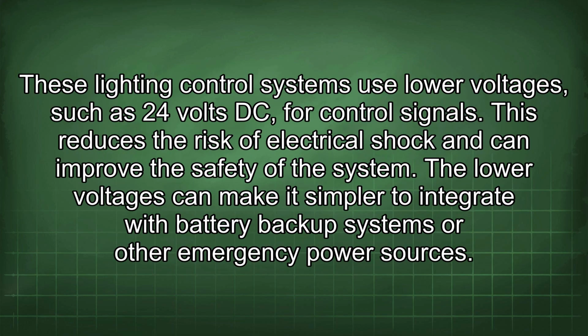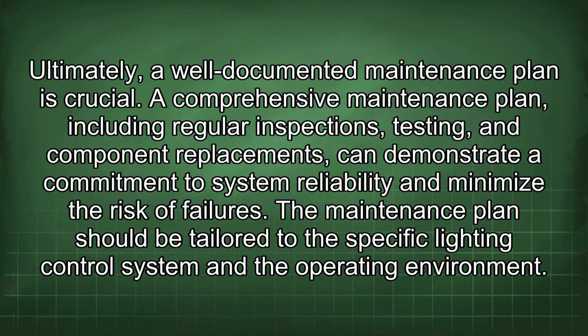These lighting control systems use lower voltages, such as 24 volts DC, for control signals. This reduces the risk of electrical shock and can improve the safety of the system. The lower voltages can make it simpler to integrate with battery backup systems or other emergency power sources. Ultimately, a well-documented maintenance plan is crucial.